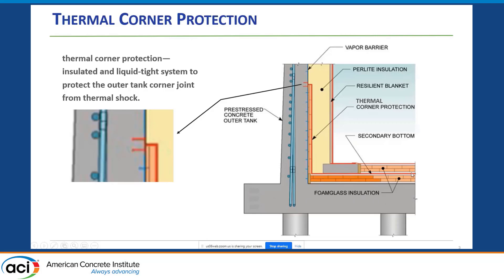One other advantage of this secondary bottom is that it provides protection if you have a small spill that could boil off and not cause further damage to the wall or the liner — the carbon steel liner. It also serves to protect the foundation from the cryogenic temperature during the spill condition, including the piles or potentially isolators that may be used in projects like John Powell described.